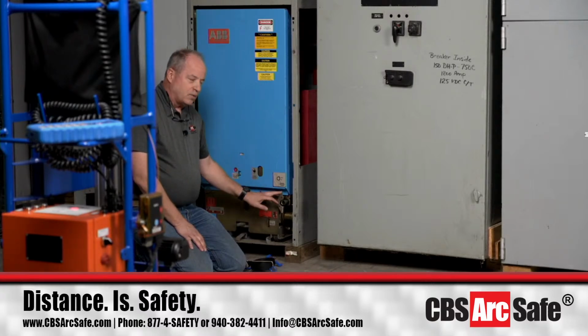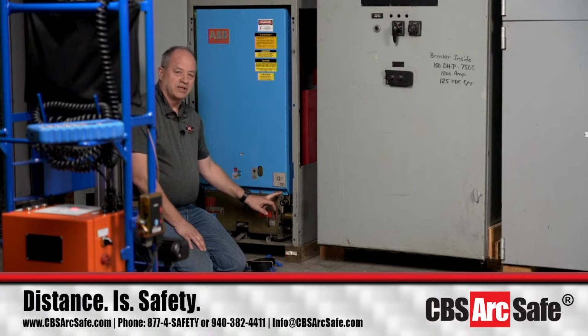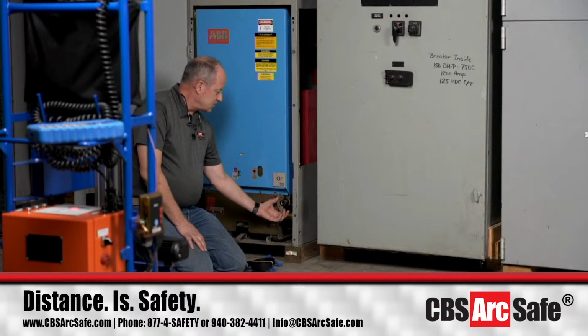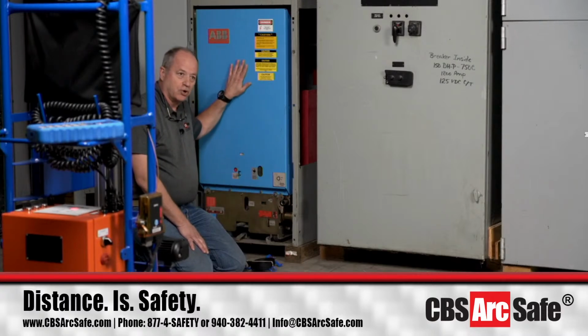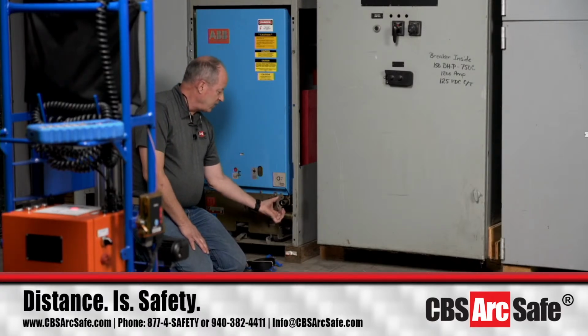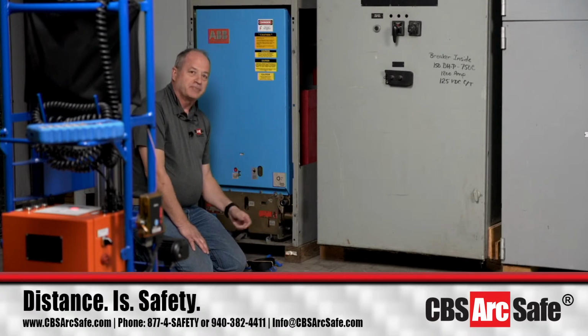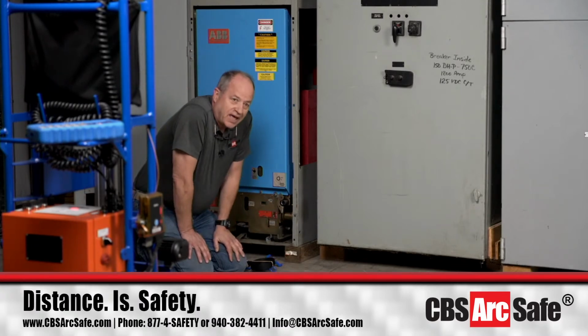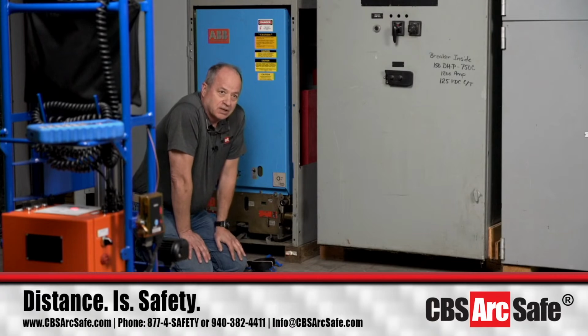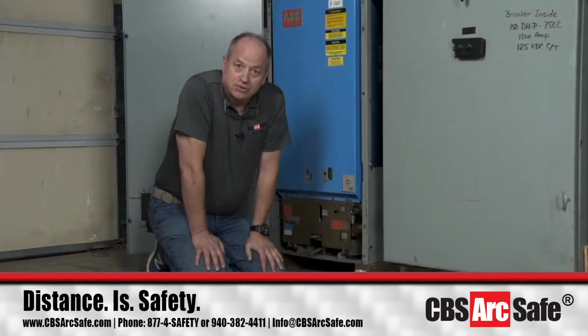Now, with these breakers, we learned a lot of stuff the first year we were doing things, and I want to share some of those things with you. When you operate the HK breaker, before I start racking this breaker at all, the first thing I'm going to do is we're going to make sure that the switchgear is open, and then I want to see manually that this latch falls back into place. If that latch doesn't fall back into place, that means that you need to get the lubricant cleaned up once we rack the breaker out.